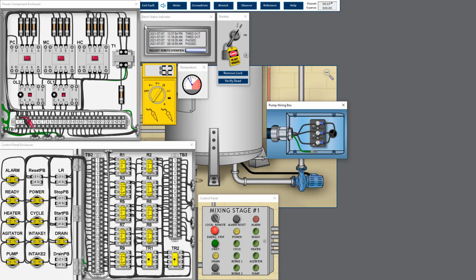So we double confirm, we check the line to line resistance of the motor. Since we already opened the junction box, we might as well check the line to line resistance in the stator winding. Alright, 16.2, looks quite balanced.